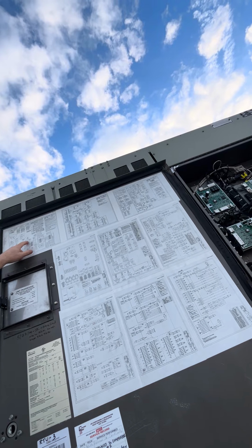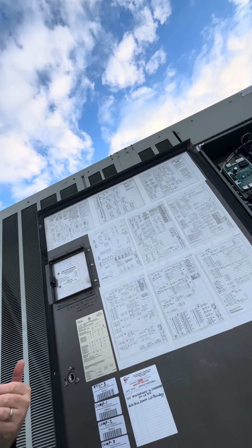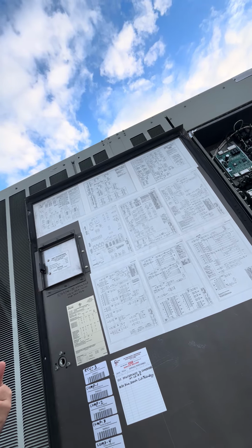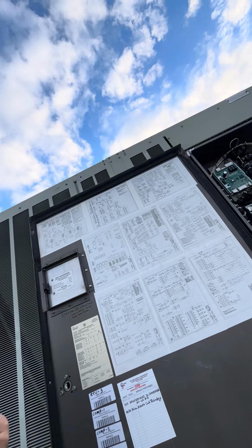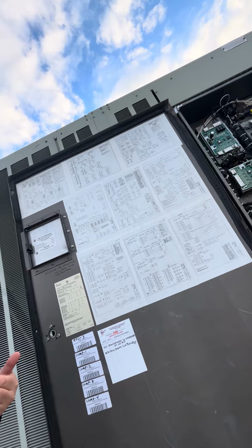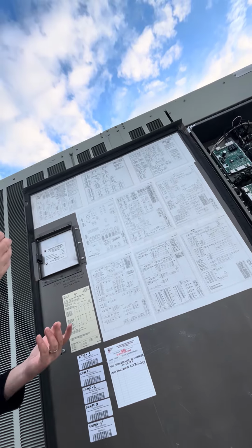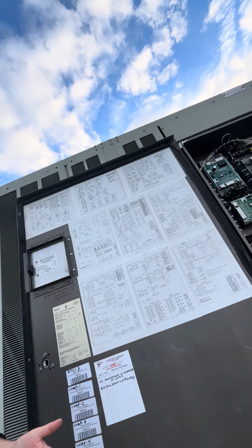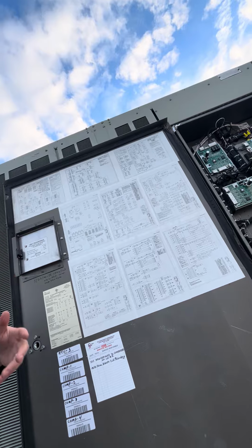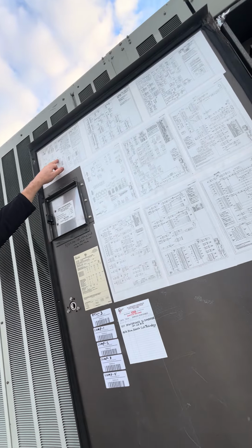It's meant for utility. If you've got a load on the grid, and we do a lot of demand response as a company, we are in contact and partnership with the utilities. They have a grid event. They ask us to shed load. So we usually will raise our set point 1 degree, or 2 degrees. And that's automatic in the system. And then, of course, that'll unload your machines or shut machines off. That's what this demand limit was intended for.